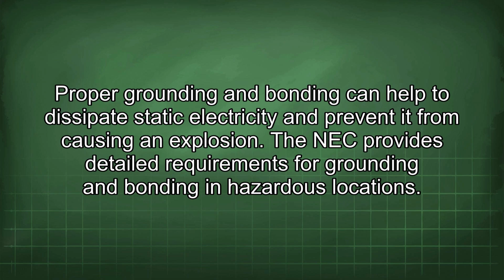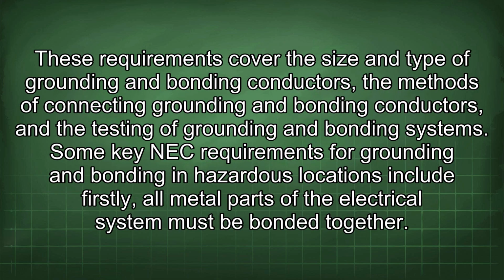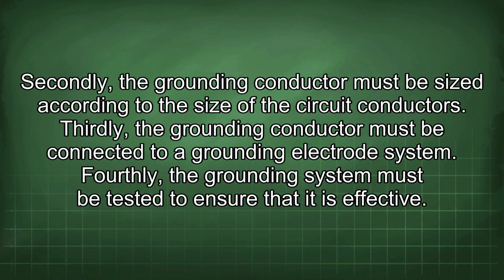The NEC provides detailed requirements for grounding and bonding in hazardous locations. These requirements cover the size and type of grounding and bonding conductors, the methods of connecting grounding and bonding conductors, and the testing of grounding and bonding systems. Some key NEC requirements for grounding and bonding in hazardous locations include: firstly, all metal parts of the electrical system must be bonded together. Secondly, the grounding conductor must be sized according to the size of the circuit conductors. Thirdly, the grounding conductor must be connected to a grounding electrode system. Fourthly, the grounding system must be tested to ensure that it is effective.